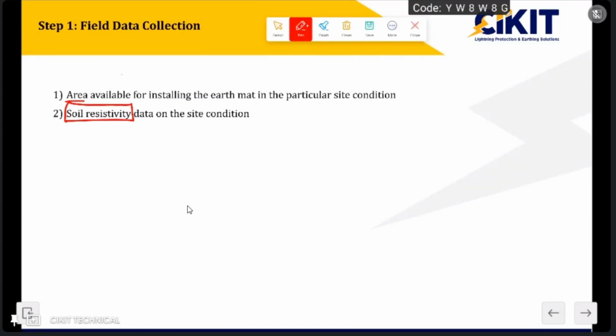As I mentioned, earthing is mainly electrolytic in nature, where the performance mainly depends upon the soil resistivity. So the first thing that we have to consider is what the soil resistivity will be on that particular site. If the soil resistivity is good, very low, it will be much easier for our design. If the soil resistivity is higher, we have to do higher calculations also. So the performance of earthing mainly depends upon the soil resistivity.